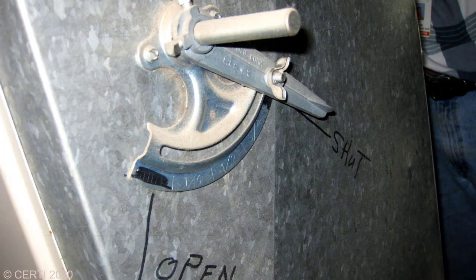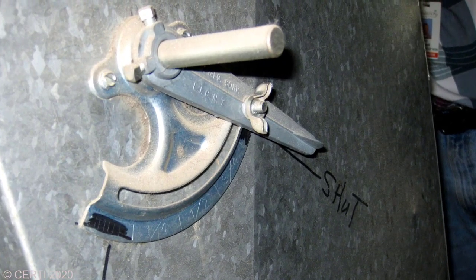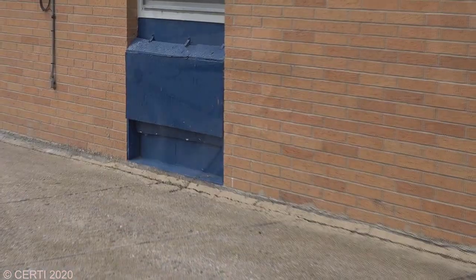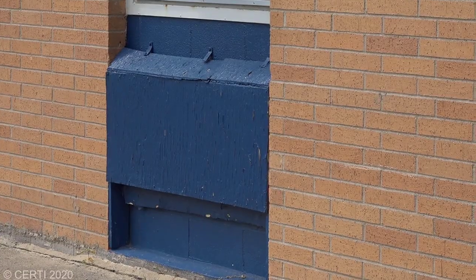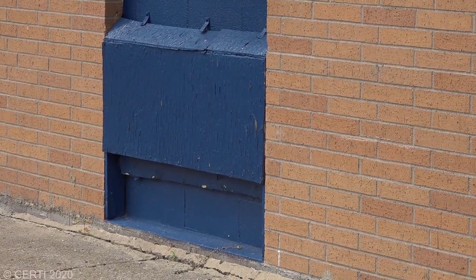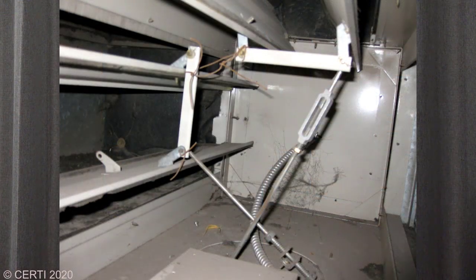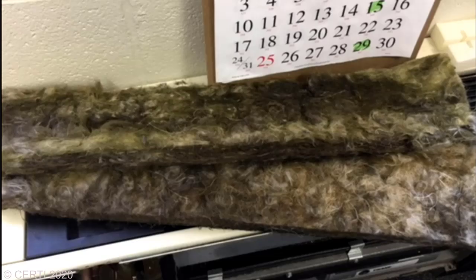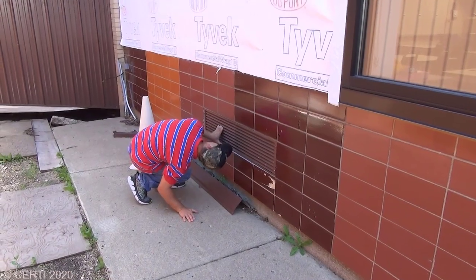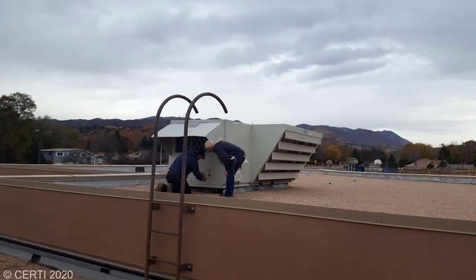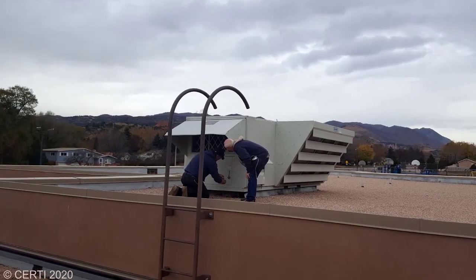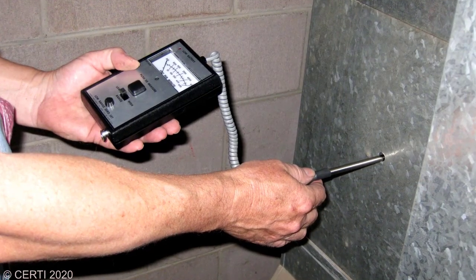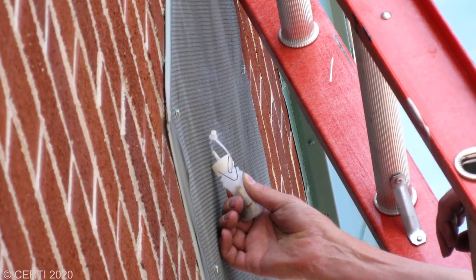Unfortunately, there may be situations where the fresh air makeup is not being provided as the HVAC system was originally designed. This may be due to air intakes being intentionally blocked to reduce energy costs for heating or cooling the outdoor air that's provided. It may also be where the damper motors that control the air intake have broken or the linkages even disabled. The amount of outdoor air can also be reduced if the filters have not been changed or the dehumidification coils have not been cleaned. In these cases, even if the outdoor air damper is open, insufficient air may be provided. It is always good to verify air is actually flowing at the design flow rate by either measuring it or using a smoke bottle to verify there's at least some air being introduced.